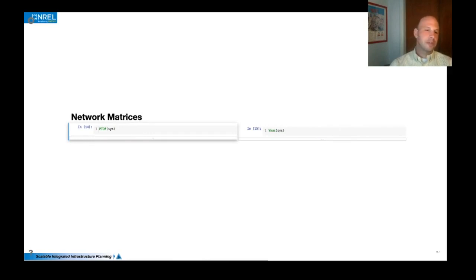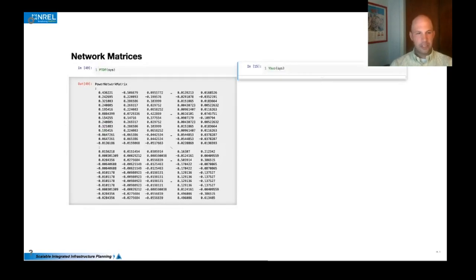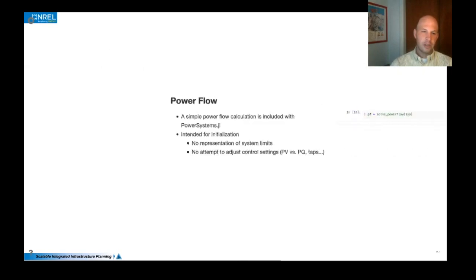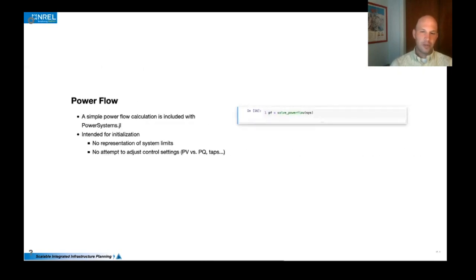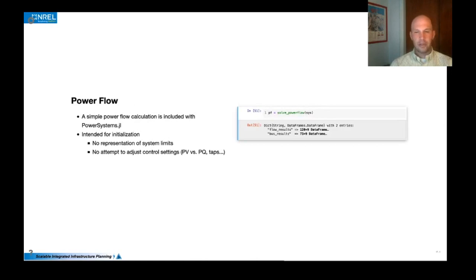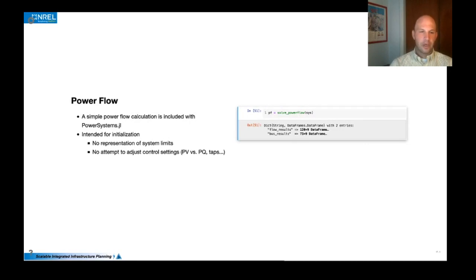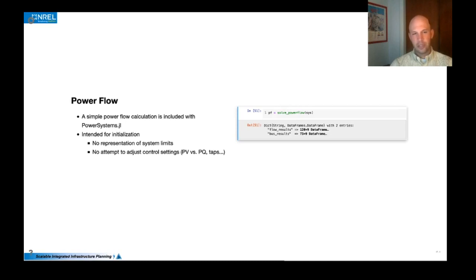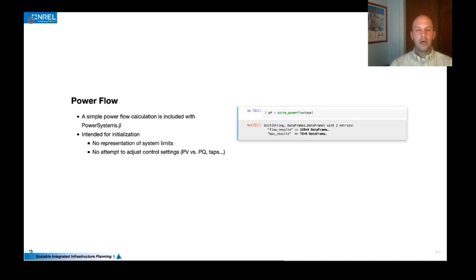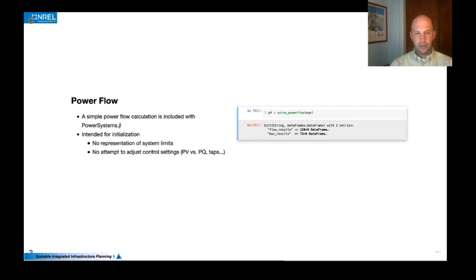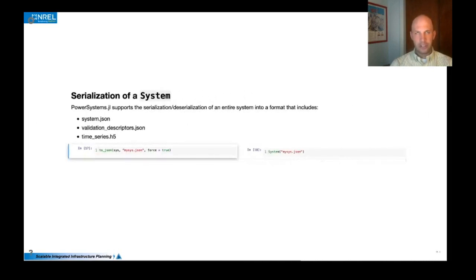Other features of power systems include standard network matrix calculations like PTDFs or YBUS. And we also have some basic power flow capability calculation capabilities where we can solve a basic Newton-Raphson power flow. It's worth noting that this power flow is not really suitable for contingency analysis because we're not really trying to represent system limits or adjusting the control settings like the PV and PQ. We are actively working on some capabilities to extend that to make a more contingency analysis appropriate power flow as well.